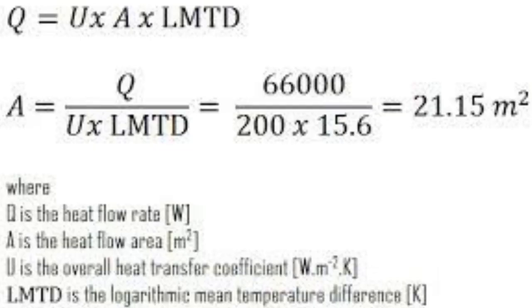The heat transfer equation is: Q = U × A × ΔT, where Q is heat in watts, U is the overall heat transfer coefficient in watts per square meter per degree Celsius, A is the surface area in square meters, and ΔT is the temperature difference between the hot and cold fluids in degrees Celsius.